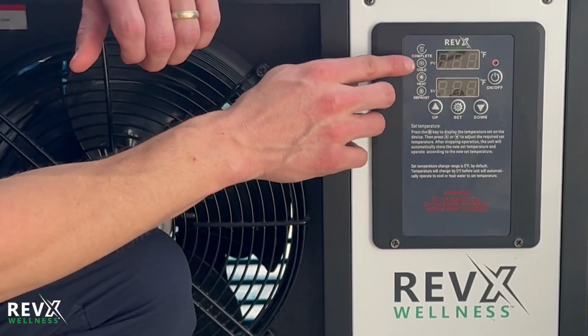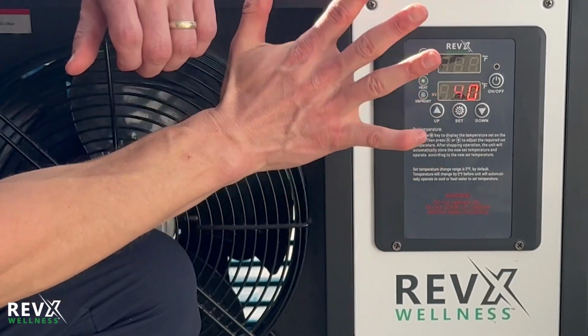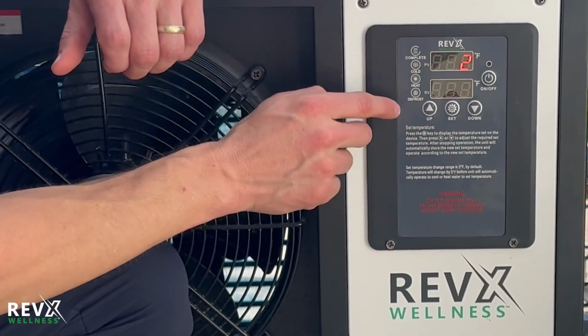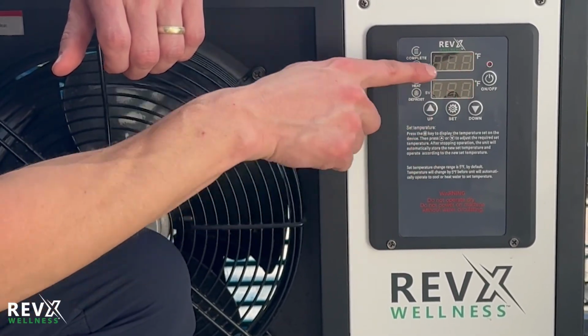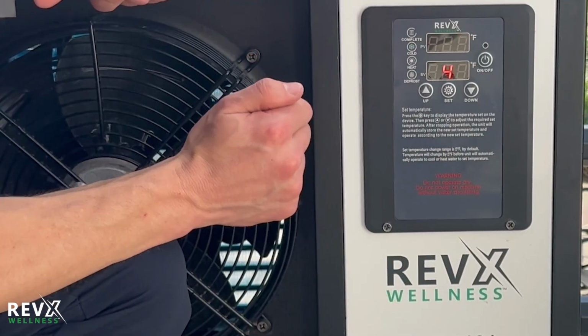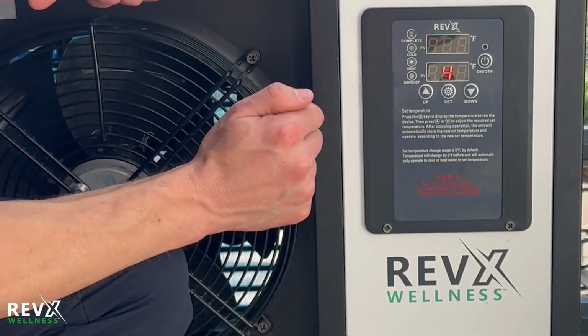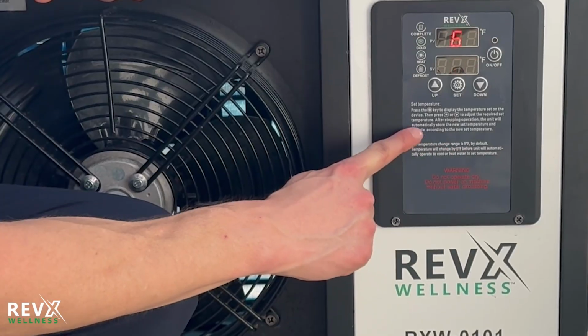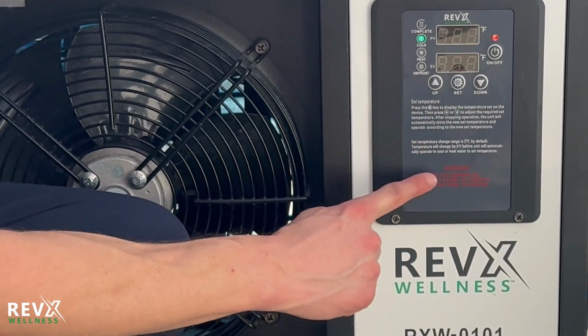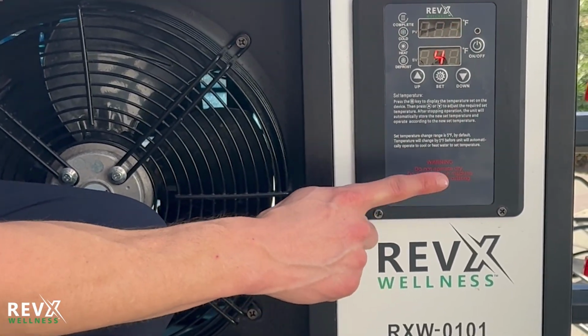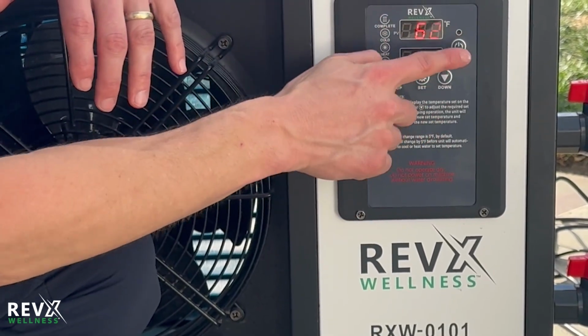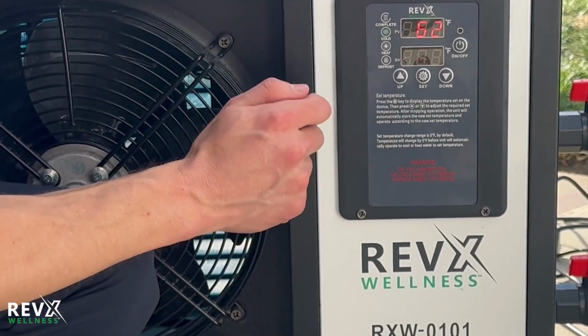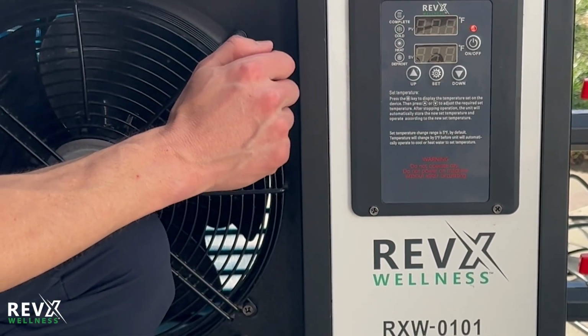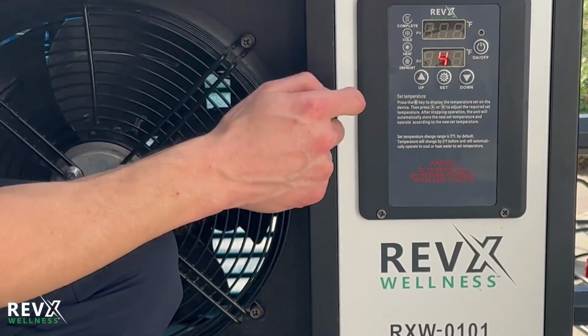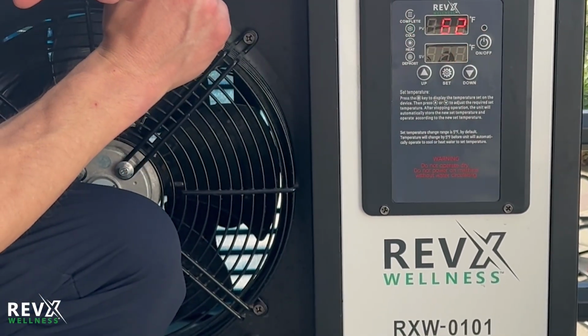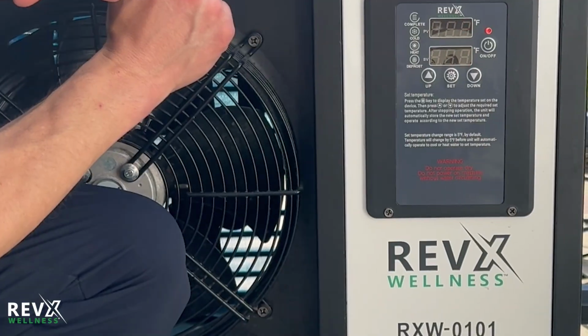And then it will wait for the present value to go up by 5 degrees to 45, and then the chiller will turn on automatically and bring it down to 40, just like the thermostat in your home for your air conditioner. This is all clearly written right here, and it also has a nice warning here that you never want to turn this chiller on if the water is not circulating, because it will damage the chiller. So never turn this chiller on unless the water pump in your filtration system is circulating the water.